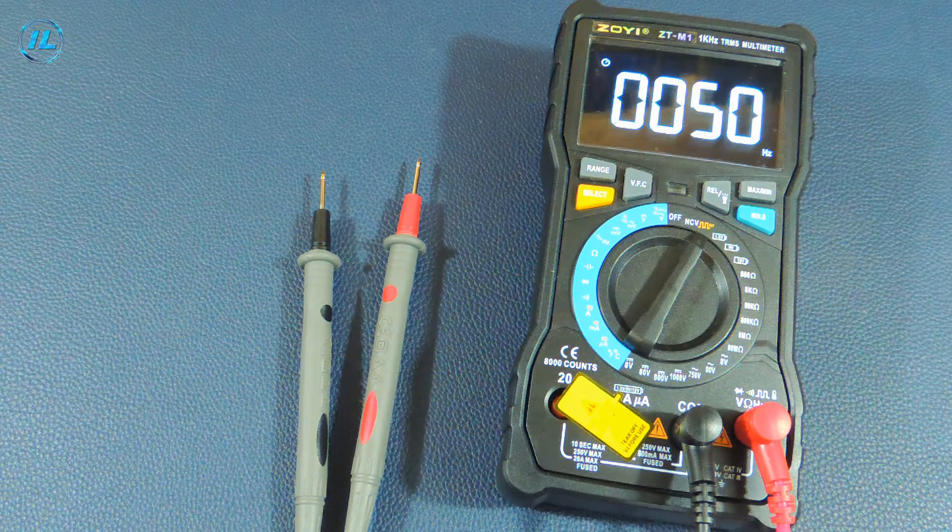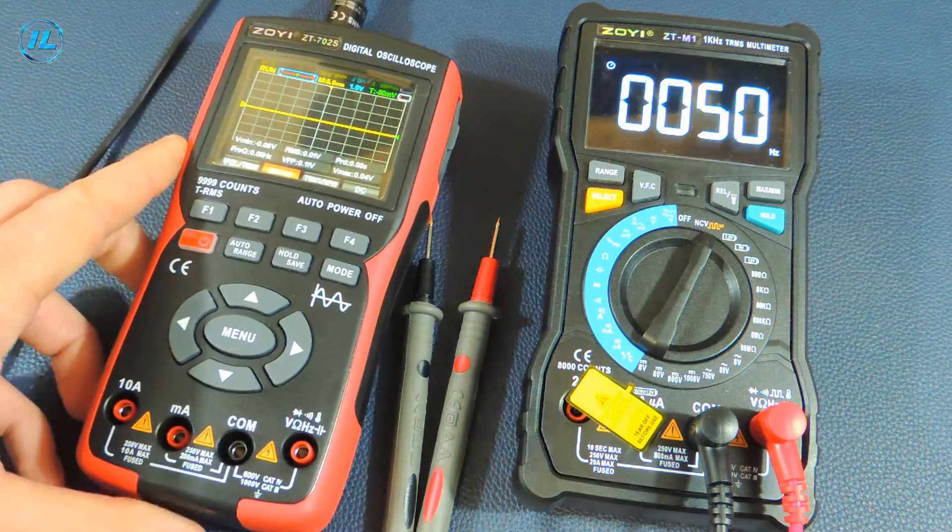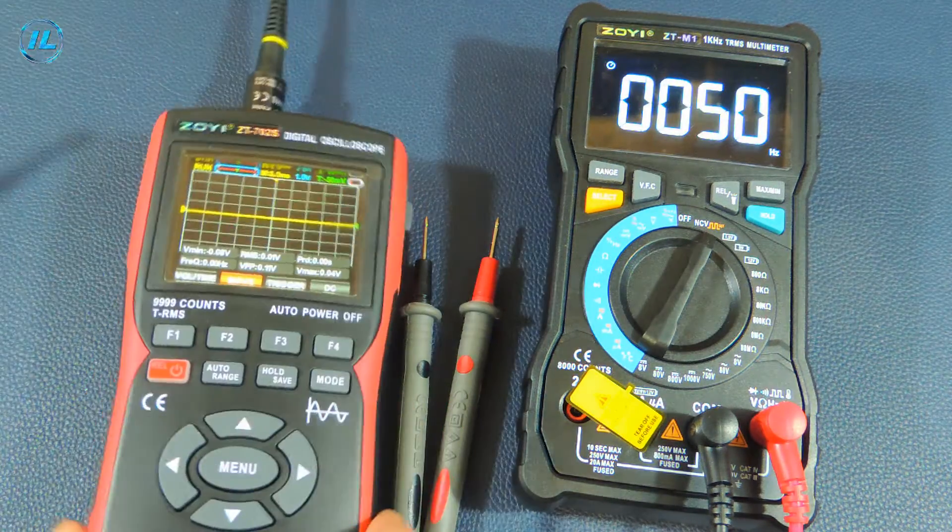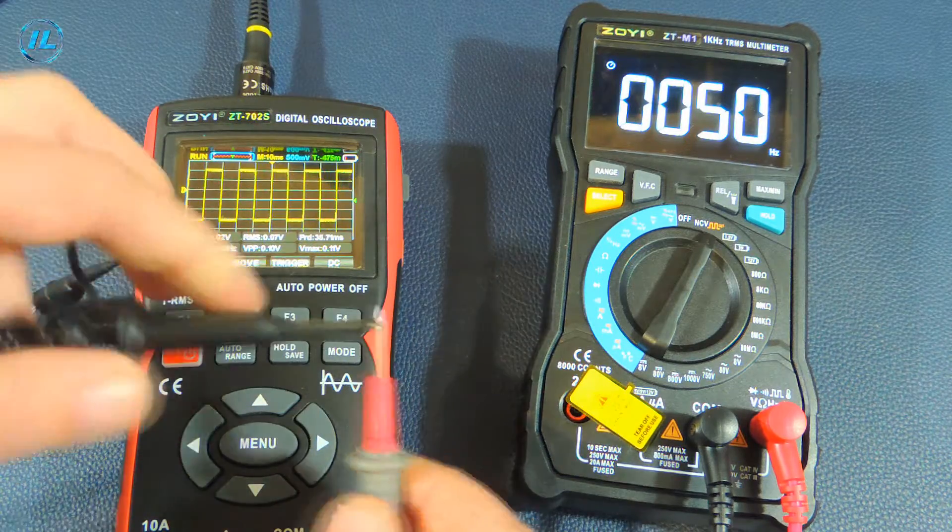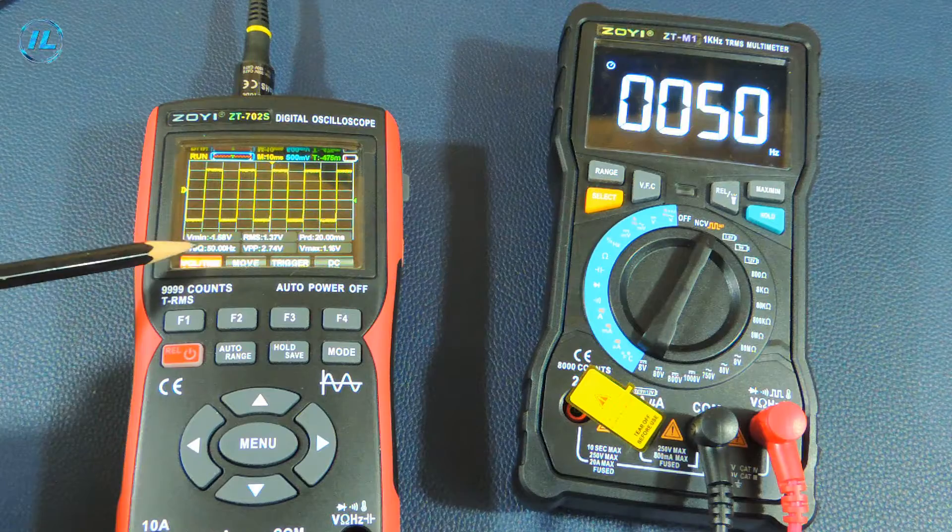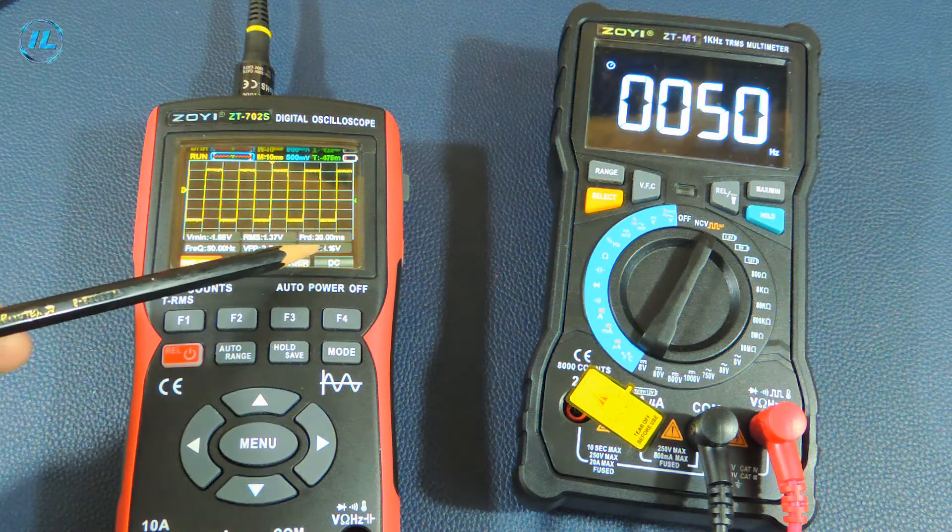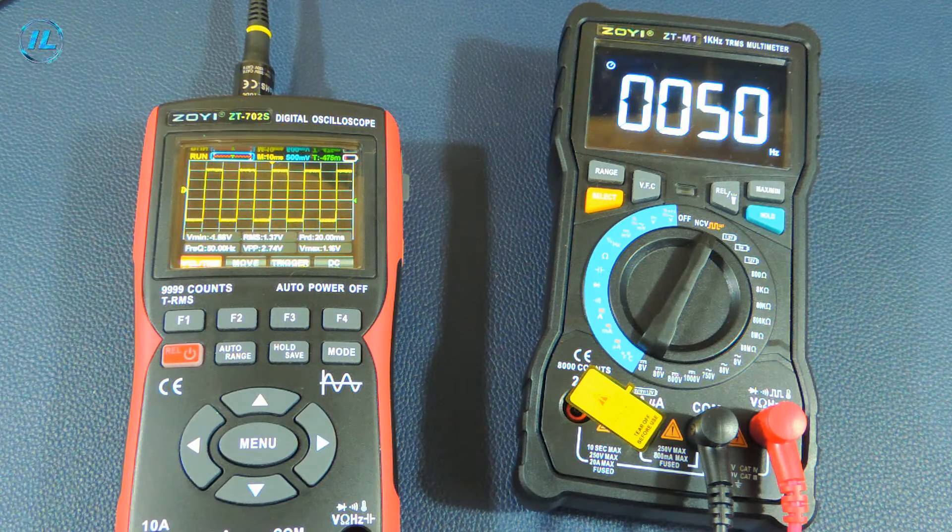The next item is the generator. The minimum frequency is 50 hertz. To test the oscillator, I will connect an oscilloscope. The output of the generator is 50 hertz. The oscilloscope shows exactly the same frequency: 50 hertz and a maximum voltage of 1.16 volts.